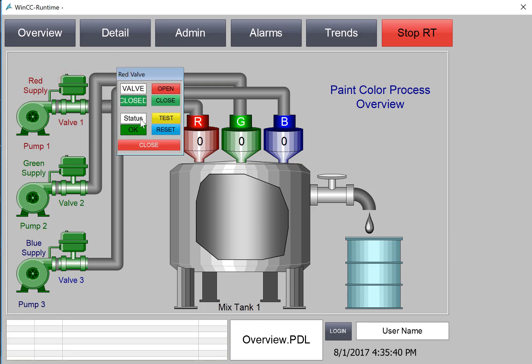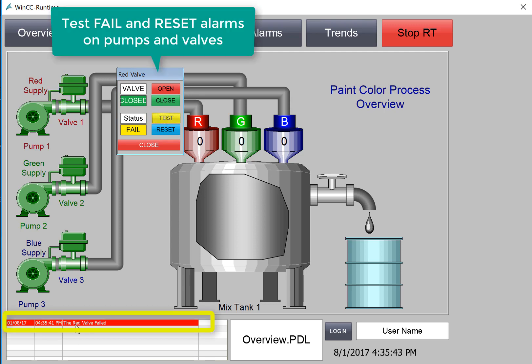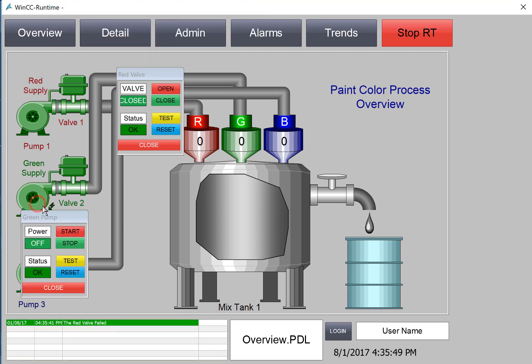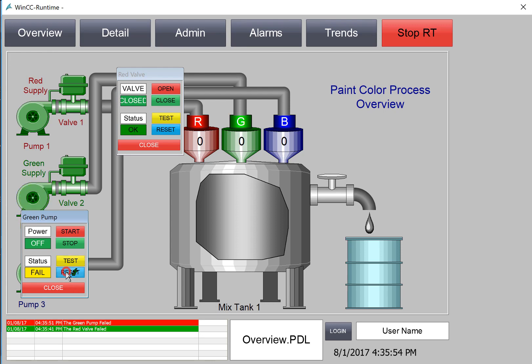So on valve one, I'll hit Test. And you can see we get our alarm here. I'll reset. And it turns green. We'll test one of the pumps. And there's our green pump fail and our reset.